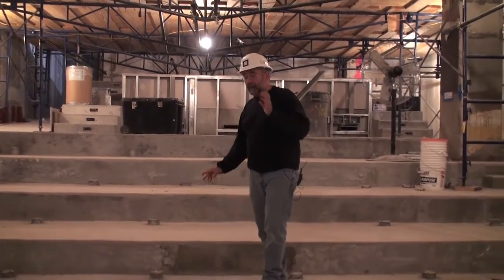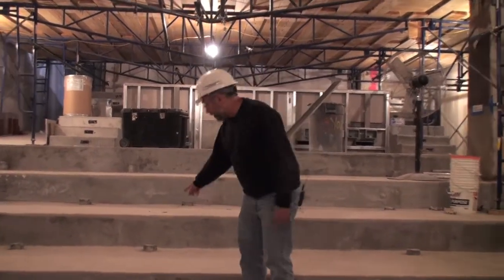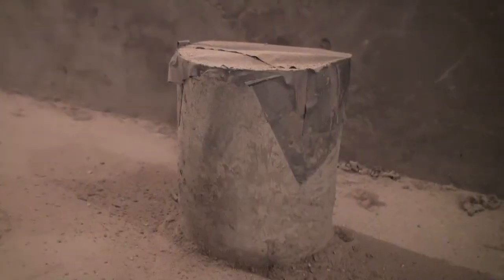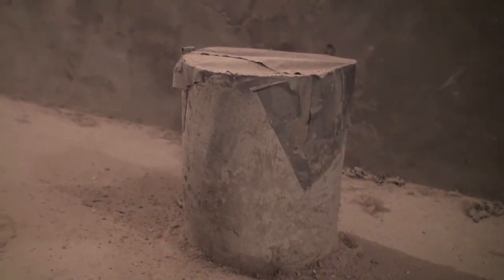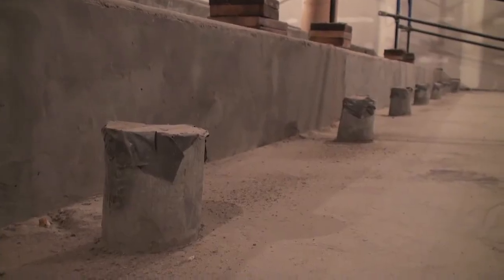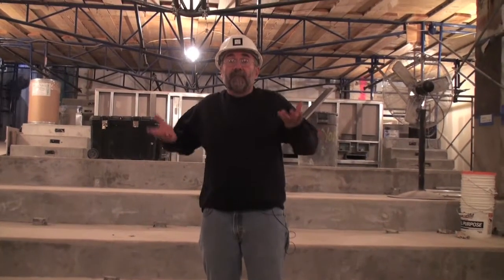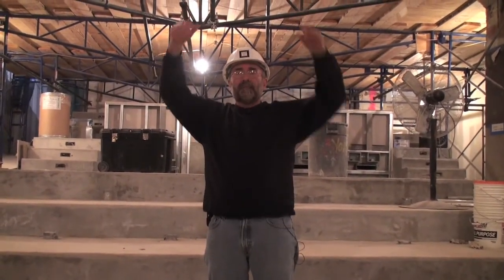One thing that is unique about this theater: you may notice these small pieces of tin ductwork coming up through the floor. That's where the supply air is going to get pulled up past the seating and brought up into the ceiling and exhausted back into the equipment.